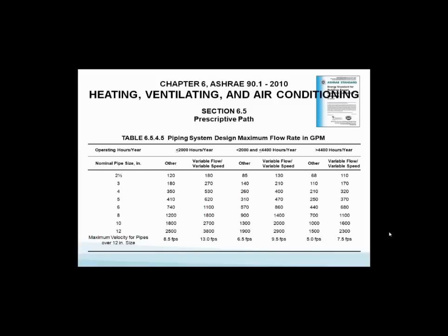This is a prescriptive path for pipe sizing for condenser water and chilled water. They're giving you pipe sizes. Take a quick look - they're giving you hours of operation per year and the maximum allowed flow in GPM through the pipe. I've never seen this done before and most engineers are not even aware. Going across the top, you'll see less than 2,000 hours to over 4,400 hours, and that changes your pipe size. Plus, it's pretty much constant flow or variable flow. Now you've got another code coming on pipe sizing that you're going to have to meet. You have no choice.